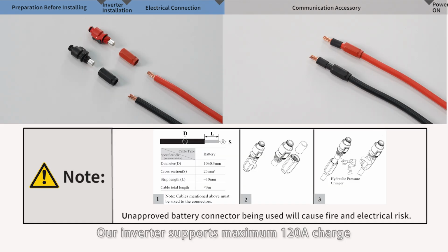Our inverter supports a maximum 120 ampere charge-discharge current. Here, we recommend 25mm squared cables for battery connection. The length of the cable should be no longer than 3 meters, and a 150 ampere external breaker should be installed. Note: an unapproved battery connector will cause fire and electrical risk.